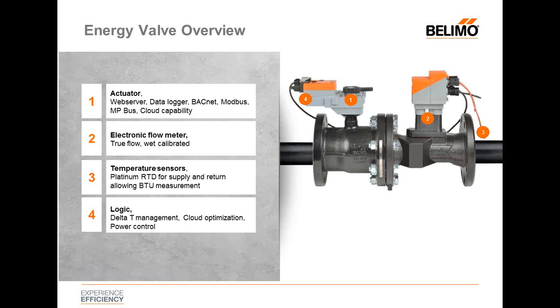We've integrated cloud optimization with an advanced analytics profile, along with core cloud services. We also have something called power control built in. You can set a flow limitation, or what we call a VMAX in a particular GPM, but you can also set a PMAX, or a power limitation, so the valve can be controlled to a specific power output as well. This makes the valve temperature and pressure independent.